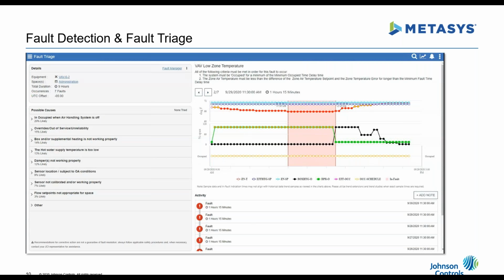What's nice about the graph, and about all of fault detection, is that once you configure the user interface for Metasys, all of this is created automatically. Nobody has to configure the screen or say what trends they want—they'll get the information related to a low zone temperature. We're utilizing a semantic database in the background to automatically populate what makes sense for this particular fault, and we do that across the board.